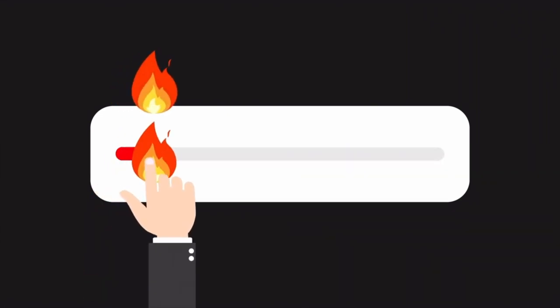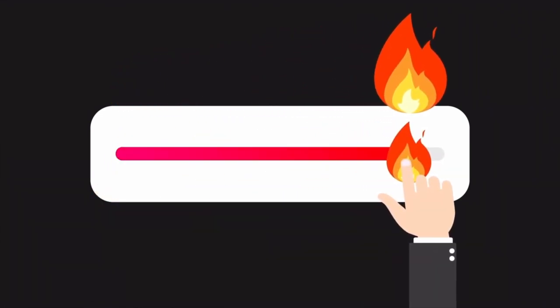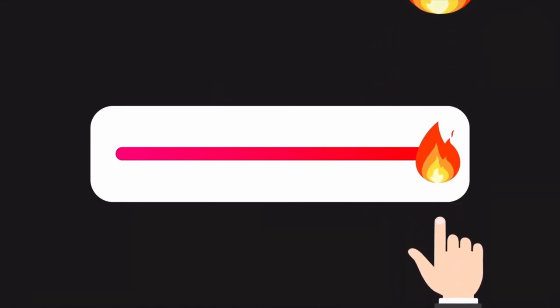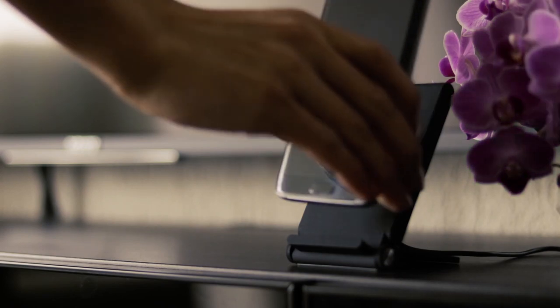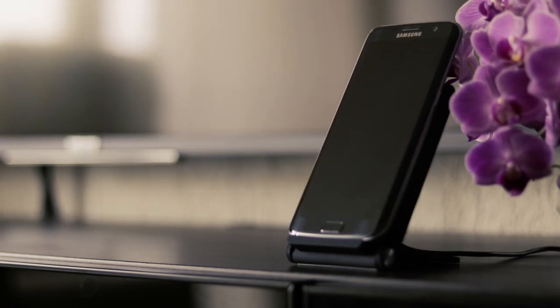Lithium-ion batteries should be operated in a range of 5 degrees Celsius to 45 degrees Celsius. If the battery temperature goes above or below this range, the battery will degrade faster and will not perform as expected. The battery temperature can go beyond 45 degrees Celsius due to improper charging, high current discharge, cumulative ambient temperature, and physical damage.